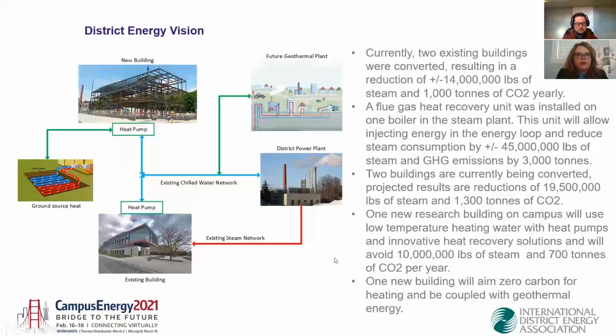So here we have the district energy vision for the future. So we have our existing chilled water network. We have external sources that we can connect to that. So for example, here a geothermal plant that we can connect in the future. We have the boiler exhaust here, and we have internal heat gains from the buildings that can all be sent to that chilled water network. So what that does is that it allows us to share energy between buildings, but it also allows us to reduce a lot the consumption of the steam plant here without even modifying the existing infrastructure. So we're keeping all that's there, and we're reusing it in a more efficient way.